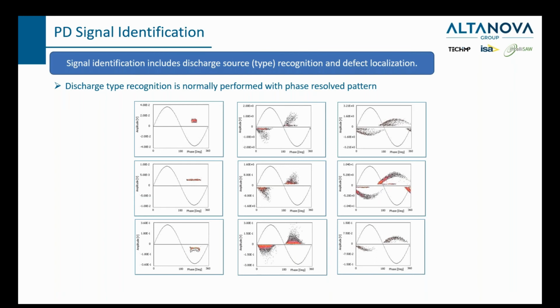As we mentioned before, different signals will have different phase resolved patterns. So here are some examples. The first column is the corona discharge. It has different shapes of distribution, but it also has its common factors: it's asymmetric, it focuses on the 27 degrees, and it's flat. The second column is the surface discharge. The third column is the internal discharge.